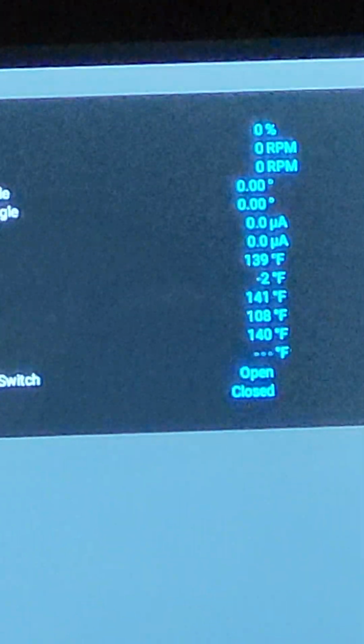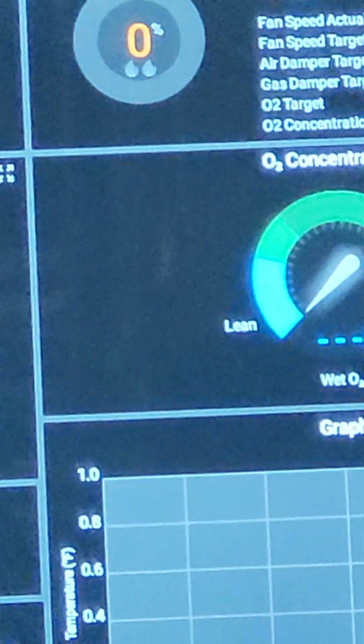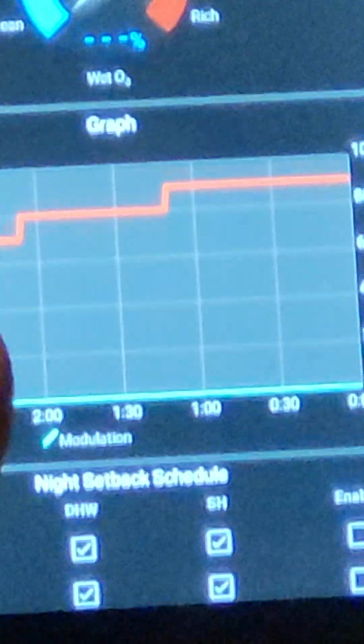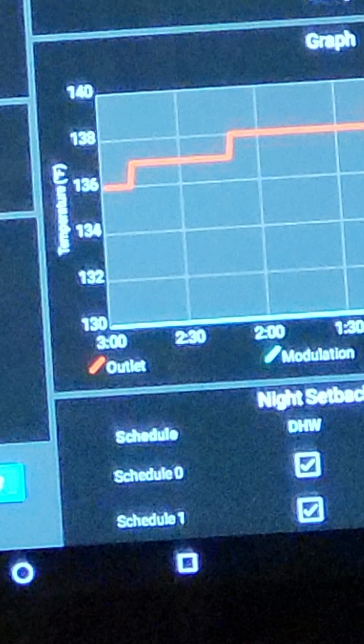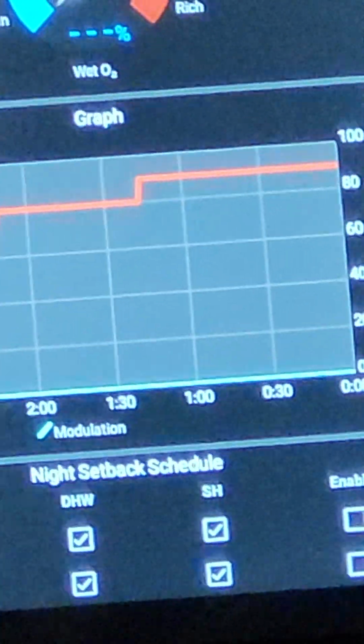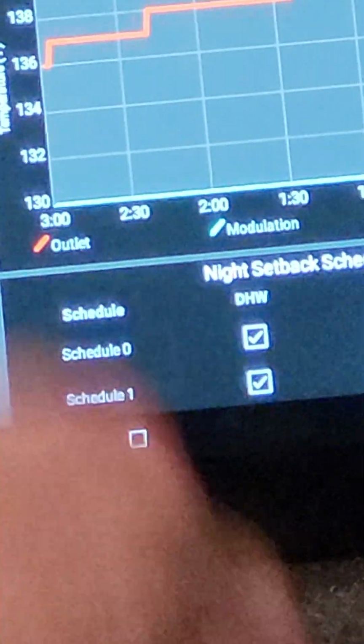If we go back to the home, you've got your boiler screen, which is on our main screen. You've got your O2 sensor there showing you where she's running, if she's lean, rich, or right in the green, which is where we want it. You've got a graph here. Let's say you had an alarm, a high limit alarm. You could graph what exactly happened in the previous 30 minutes before that alarm happened.